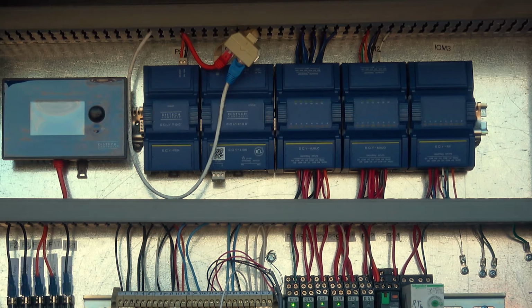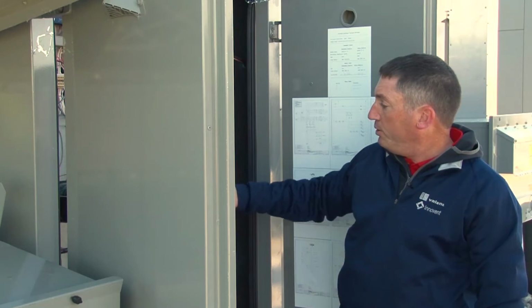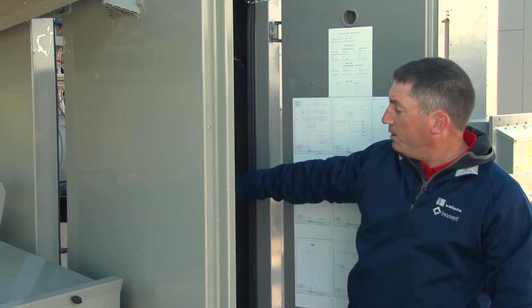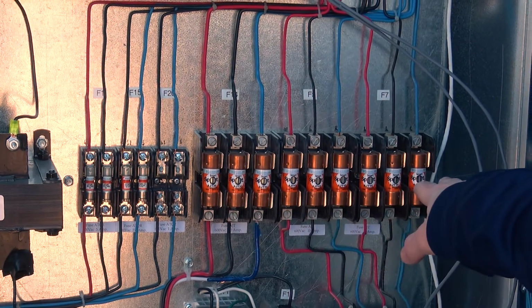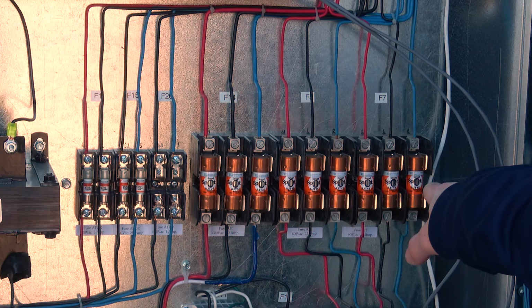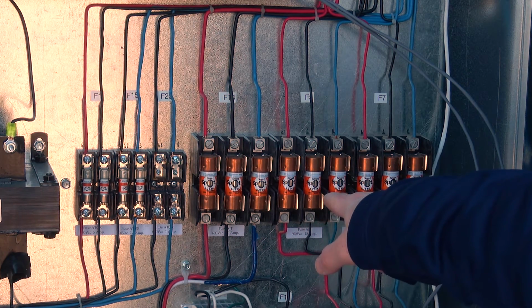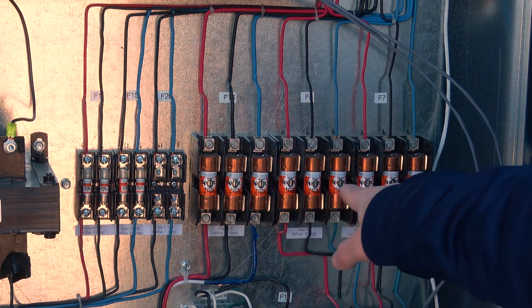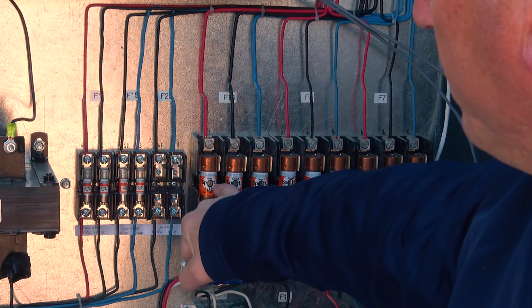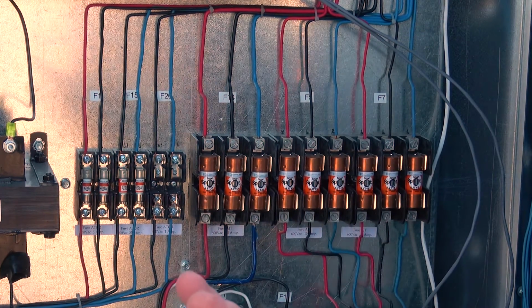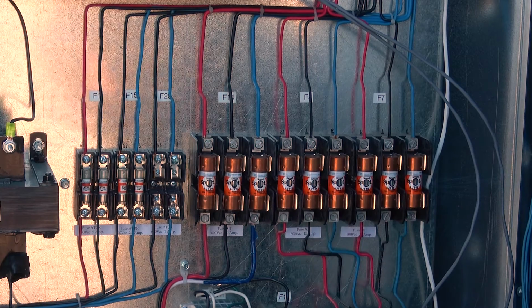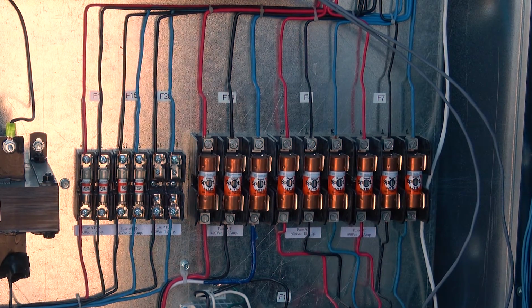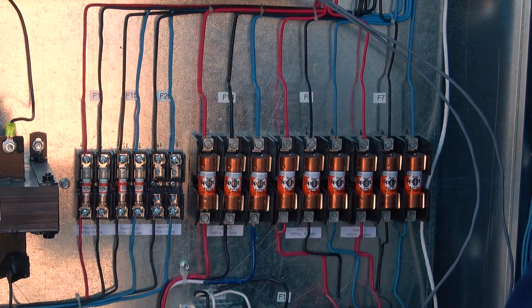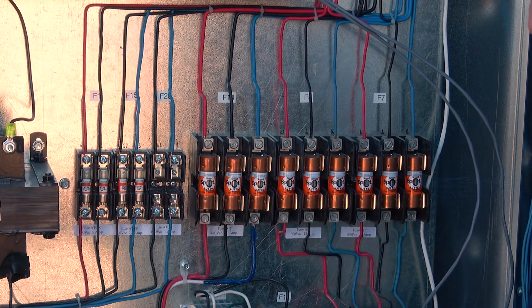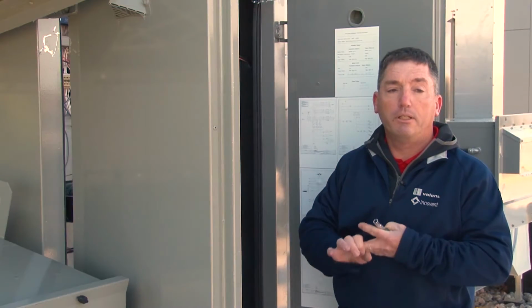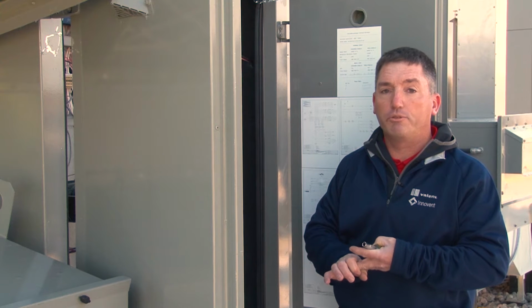The information you're going to get out of this PLC here is more to assist a technician when they're diagnosing an issue. Other things to look for, you'll see there's several banks of fuses. The large copper fuses are what we call the smart spots. If you notice that this center section here is either black or red, that's an indication that that fuse has blown, and chances are something downstream, motor, condensing unit, etc., isn't going to be functioning until that fuse is replaced.